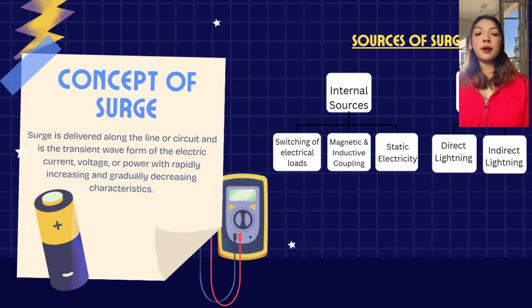The first type is the internal sources, and the second type is the external sources. The internal sources originate within the electrical system, which are, first, switching of electrical loads, for example, turning machines on or off. Second, magnetic and inductive coupling, and third, static electricity. The second main category is the external sources. These come from outside the system. It has two main types, direct lightning and indirect lightning. External sources are usually more dangerous because they involve very high energy.